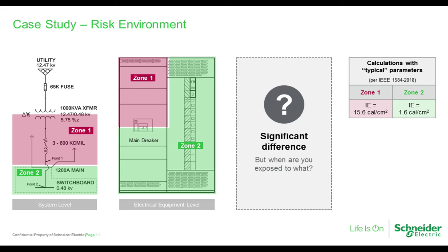In this case, the incident energies are 15.6 calories per centimeter squared in zone 1 and 1.6 calories per centimeter squared in zone 2. The difference is essentially the difference between the clearing time of the 65 kA fuse and the 1200 amp main. So we can see, and it is generally the case, that the risk environment is not uniform, and the risks on the line side of the incoming breaker, as demonstrated in the one line and in the equipment image, are generally higher.